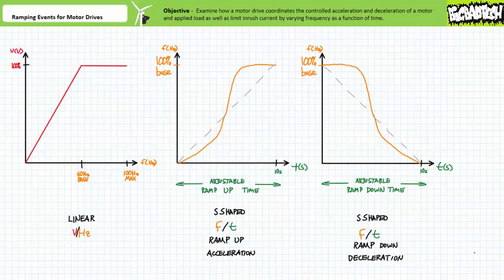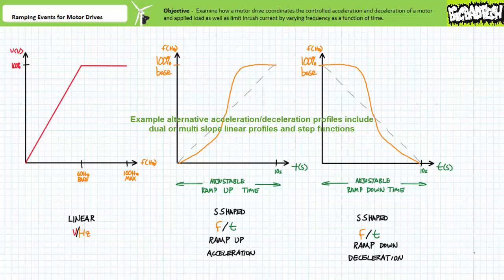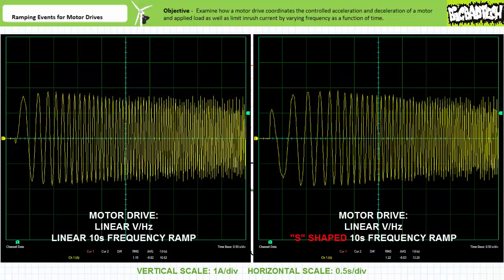Note that not all acceleration and deceleration frequency as a function of time patterns are linear. Consider, for example, an S-shaped frequency as a function of time profile. S-shaped curves are commonly used for applied loads that need to be briskly accelerated to high speed and then rapidly decelerated to a stop. The classic example of an S-shaped acceleration or deceleration profile is the feeling you might get in an elevator traveling between floors. A user can ordinarily customize the time it takes to execute the S-shaped acceleration or deceleration period. Depending upon the particular motor drive employed, more or fewer acceleration and deceleration patterns and options may be available for specific applications. A graph of line current for a motor drive using a linear volts per hertz ratio and a linear 10-second ramp-up time appears next to one employing a linear volts per hertz ratio and an S-shaped 10-second ramp-up time. The S-shaped acceleration profile shows frequency starts low and then rapidly transitions to full speed.